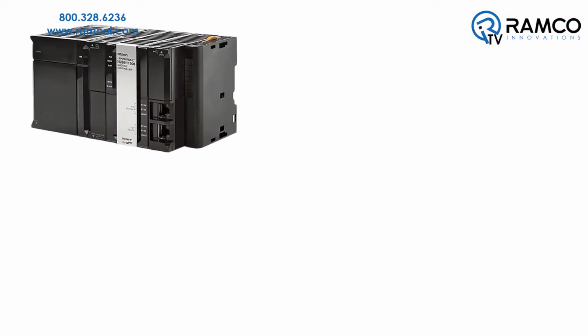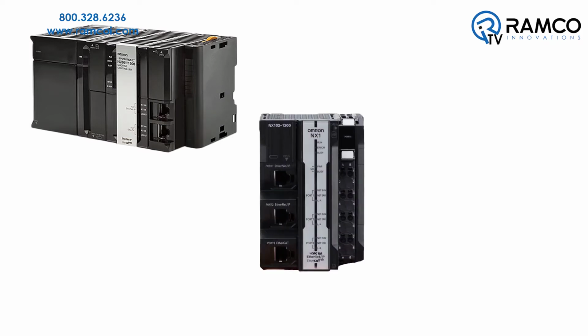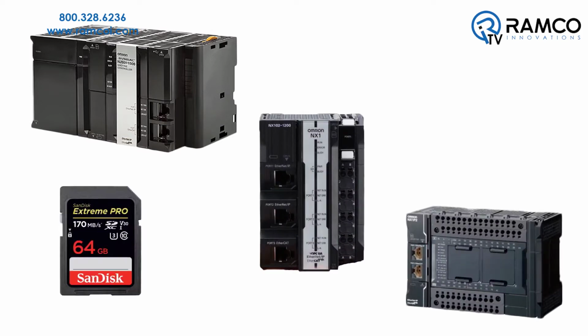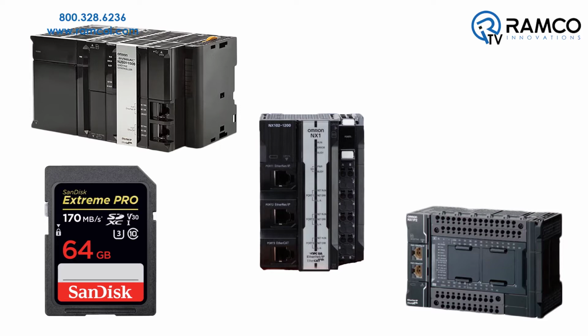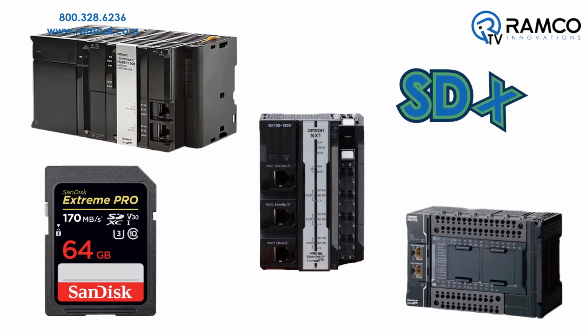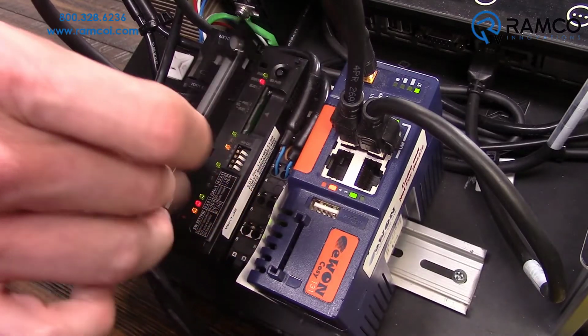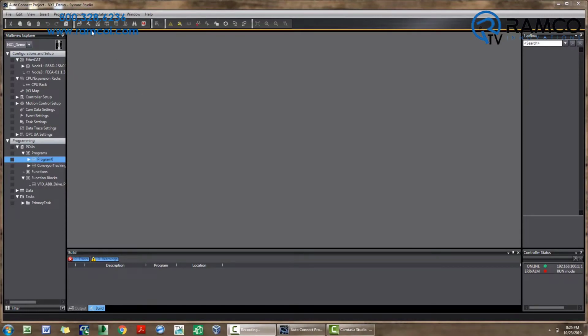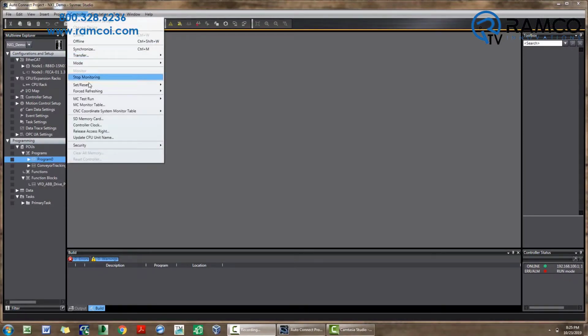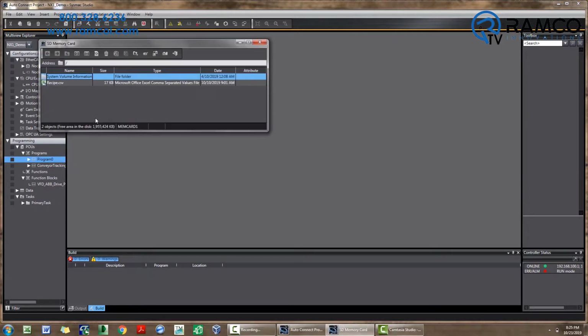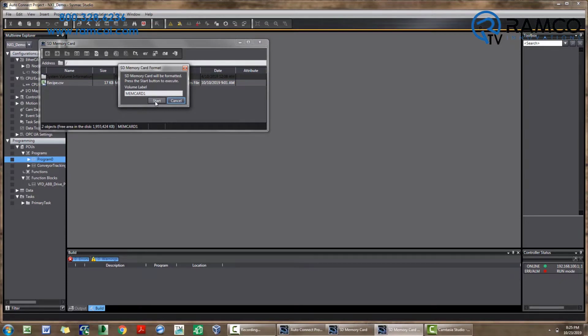If you have an NJ, there is an SD card already present. With an NX1 or NX1P2, you must purchase an SD card separately. All the processors use a standard SDXC SD card. When you purchase a new SD card, you must format it so the processor can read it. To do this, insert the SD card in the appropriate slot. Go online with your processor. From the controller, go to SD memory card. Then choose Initialize SD card and Start. Now your SD card is ready.